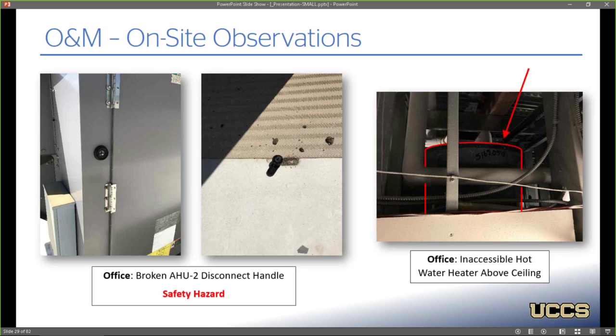The electric hot water heaters are installed up in the ceiling, and it's a little hard to see in that photo, but I drew a little outline. That is as close as I could get to that hot water heater. So again, it's not really an energy issue, but certainly a service concern. If that thing were to fail and need to get replaced, that would be extremely difficult.